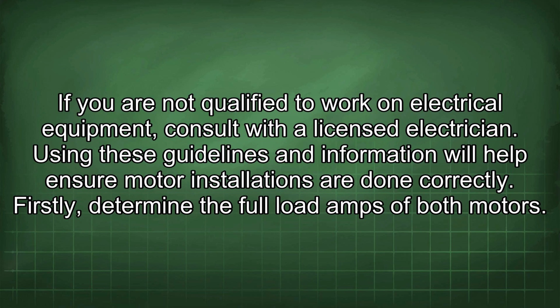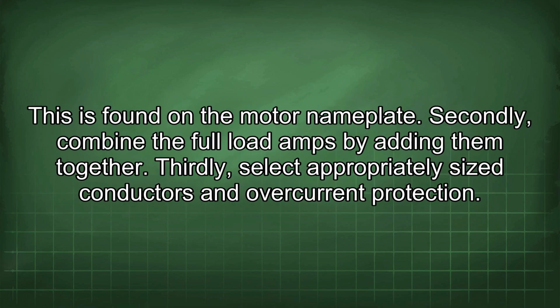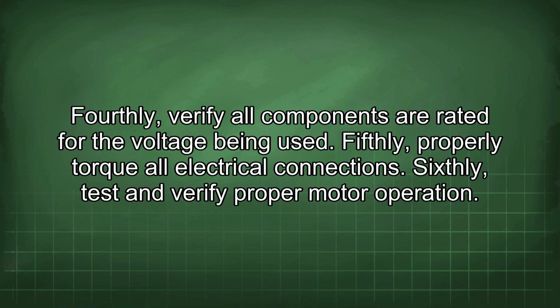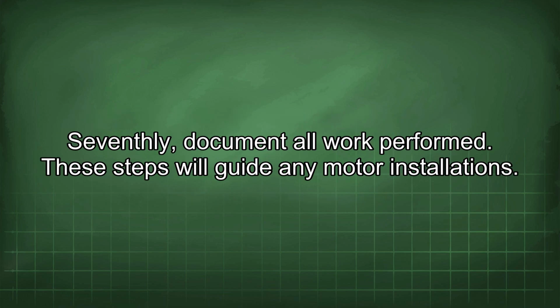Firstly, determine the full load amps of both motors. This is found on the motor nameplate. Secondly, combine the full load amps by adding them together. Thirdly, select appropriately sized conductors and overcurrent protection. Fourthly, verify all components are rated for the voltage being used. Fifthly, properly torque all electrical connections. Sixthly, test and verify proper motor operation. Seventhly, document all work performed. These steps will guide any motor installations.